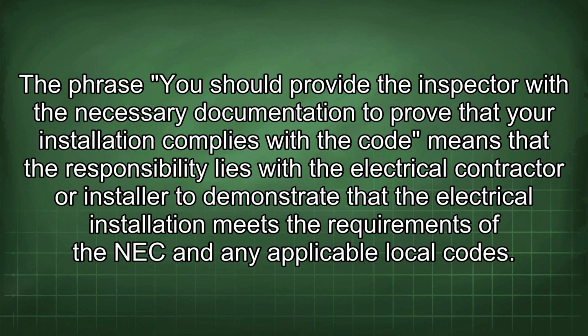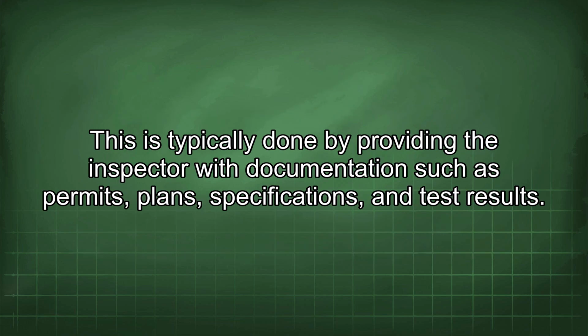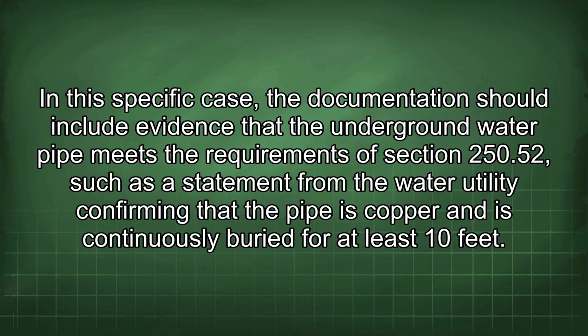The phrase "you should provide the inspector with the necessary documentation to prove that your installation complies with the code" means that the responsibility lies with the electrical contractor or installer to demonstrate that the electrical installation meets the requirements of the NEC and any applicable local codes. This is typically done by providing the inspector with documentation such as permits, plans, specifications, and test results. In this specific case, the documentation should include evidence that the underground water pipe meets the requirements of section 250.52, such as a statement from the water utility confirming that the pipe is copper and is continuously buried for at least 10 feet.